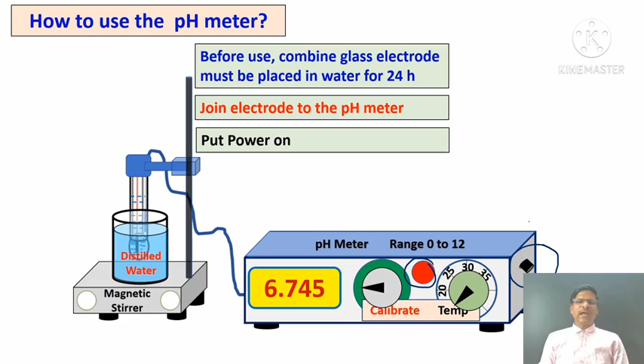a pH meter cannot be used without calibration. So the next step is the calibration of the pH meter, and the very first step is to adjust the temperature knob to the room temperature or the temperature of the water or the buffer solution. This is the temperature knob, and suppose today's temperature is 25 degrees Celsius. I will adjust this knob to 25 degrees Celsius.